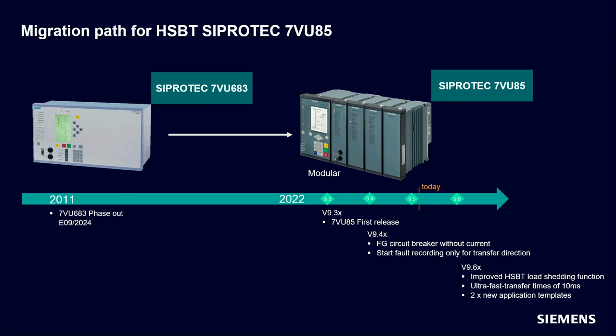With 9.40, we introduced some improvements for the function group circuit breaker without current. We also improved the fault recording, so that only the fault recorder is starting for the used transfer directions. And with the 9.60, this is a little bit the outlook for our 7VU85, we improved the load shedding functionality, and we have the new ultra-fast transfer algorithm. And in the end, with the 9.60, we also implement two new application templates for this new device type.